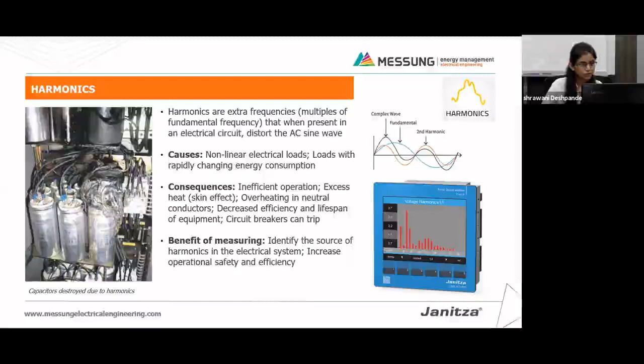The consequences of harmonics include overheating of the equipment, and due to overheating, it causes reduced efficiencies and reduced lifespan of certain equipment such as transformers or motors. Then another important consequence is the skin effect. Skin effect in case of cables causes insulation degradation. And due to insulation degradation, the life of that cable reduces. Let's say a cable is supposed to work for 10 years and due to this insulation degradation, it might end up lasting, let's say, 7 years. So it is again a loss that you will have to pay for.